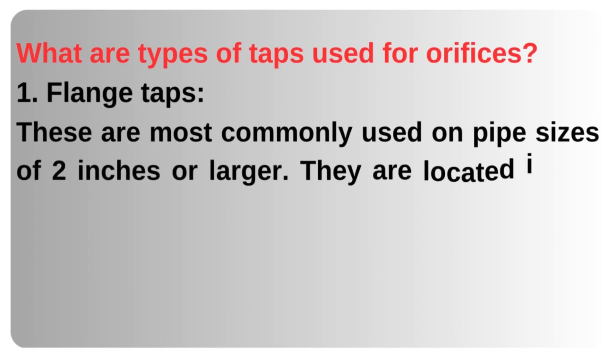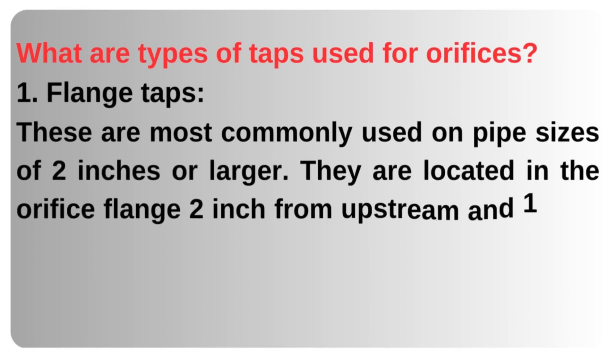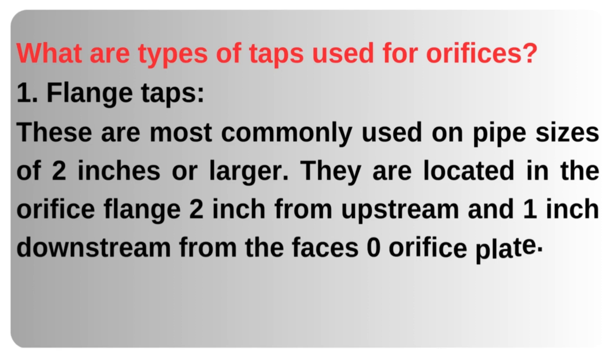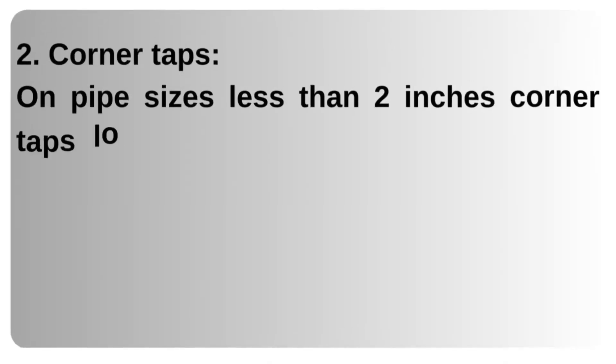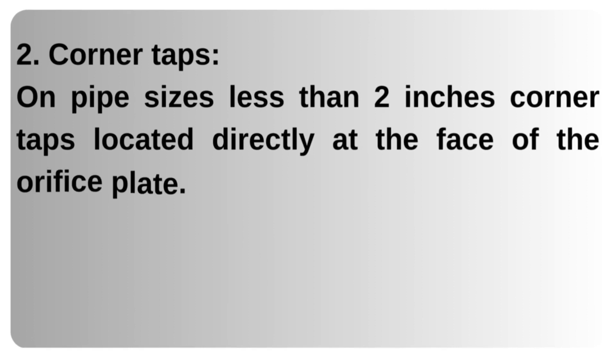What are the types of taps used for orifices? 1. Flange taps — these are most commonly used on pipe sizes of 2 inches or larger. They are located in the orifice flange, 2 inches upstream and 1 inch downstream from the face of the orifice plate. 2. Corner taps — on pipe sizes less than 2 inches, corner taps are located directly at the face of the orifice plate.